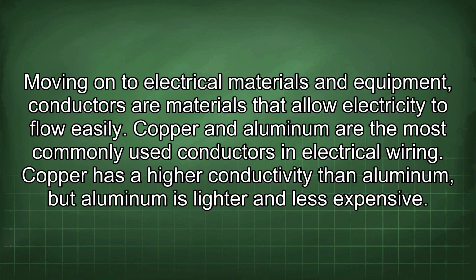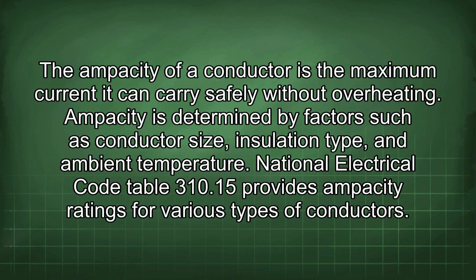Moving on to electrical materials and equipment, conductors are materials that allow electricity to flow easily. Copper and aluminum are the most commonly used conductors in electrical wiring. Copper has a higher conductivity than aluminum, but aluminum is lighter and less expensive. The ampacity of a conductor is the maximum current it can carry safely without overheating. Ampacity is determined by factors such as conductor size, insulation type, and ambient temperature. National Electrical Code Table 310.15 provides ampacity ratings for various types of conductors.